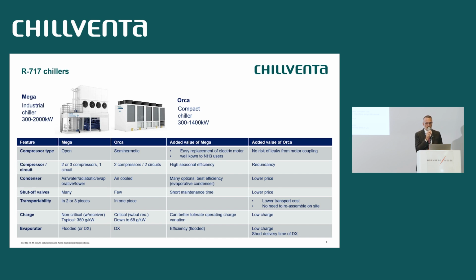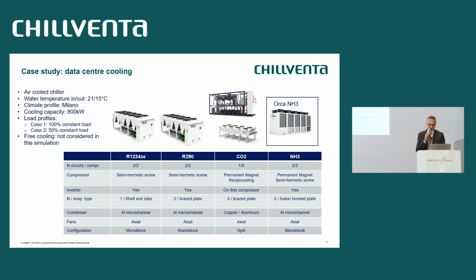So the main differences between these 2 chillers is clearly on the condenser side, because the Orca is a conventional air-cooled chiller. And also the compressor. The compressor is a semi-hermetic type, which means the motor is inside the casing, and it means there is absolutely no risk of ammonia leaks from the motor coupling. And clearly, the most important advantage is the low refrigerant charge. So you remember at the beginning I mentioned that we can go as low as 65 grams per kilowatt. So for customers who are not familiar with ammonia, and they are concerned about the refrigerant charge, this is the solution.